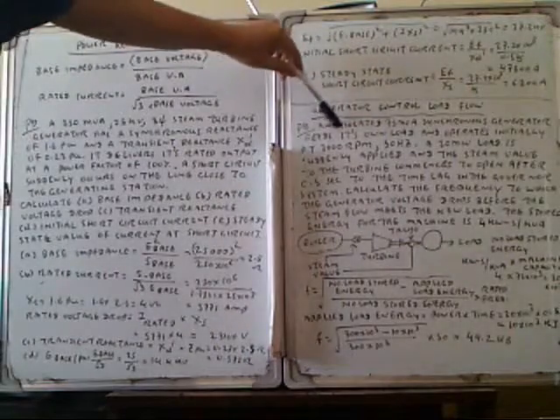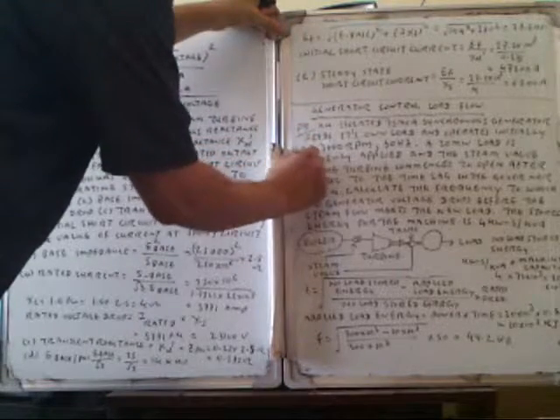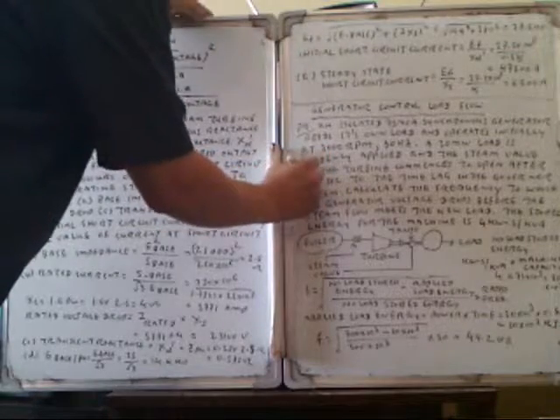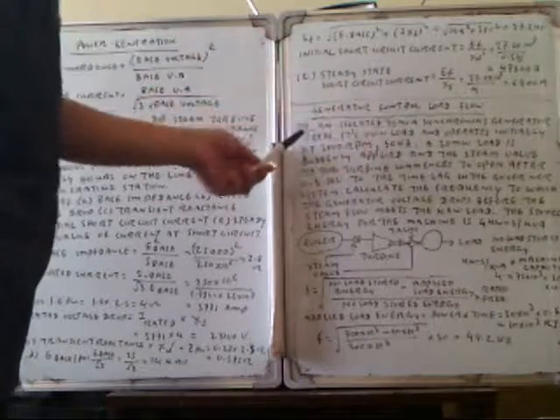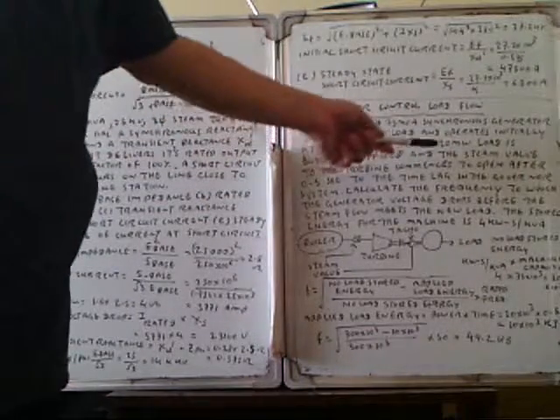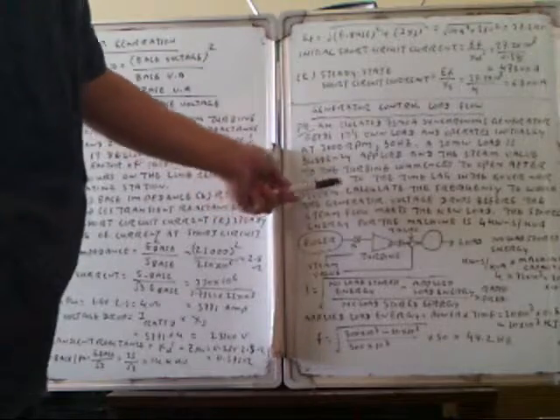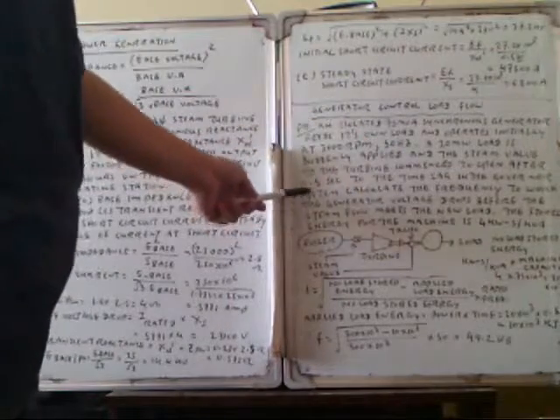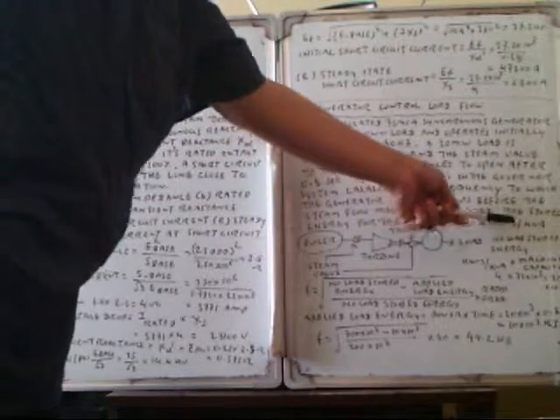The problem involves an isolated 75 MVA synchronous generator feeding its own load, initially operating at rated speed of 3,000 rpm at 50 Hz. A 20 MW load is suddenly applied, and the steam valve takes one second — with a 0.5 second delay in the governor system. Calculate the frequency to which the generator drops before steam flow meets the new load. The stored energy is 4 kW·s per kVA.